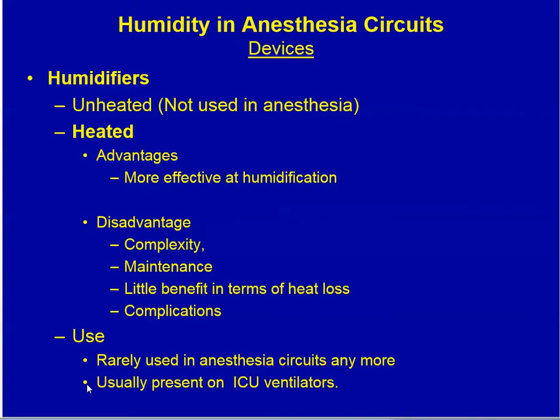Other devices to warm and humidify breathing gases are humidifiers, which can be unheated or heated. The advantage is more effective humidification, but the disadvantages are complexity, maintenance, little benefit in terms of heat loss, and potential complications. Although commonly used 10 to 15 years ago in anesthesia circuits, they are rarely used anymore in anesthesia, but are usually present in ICU ventilators.